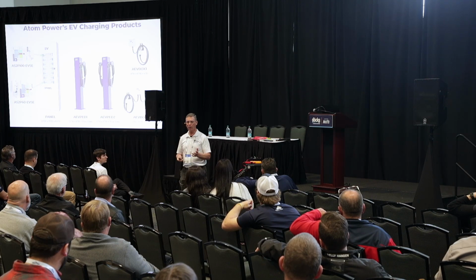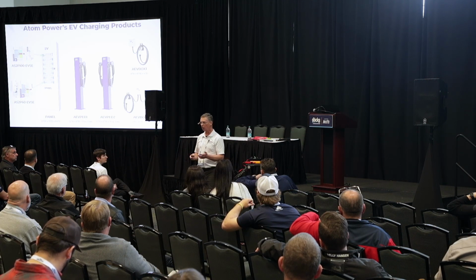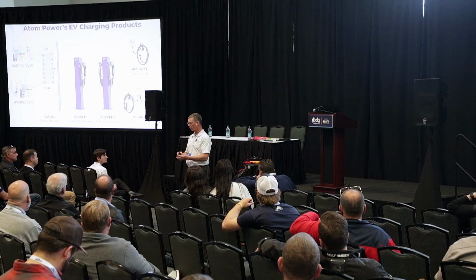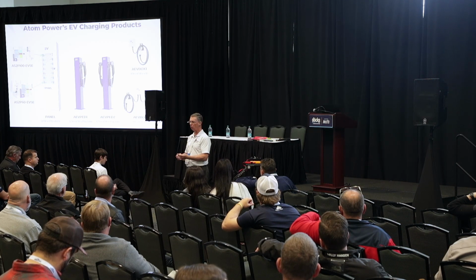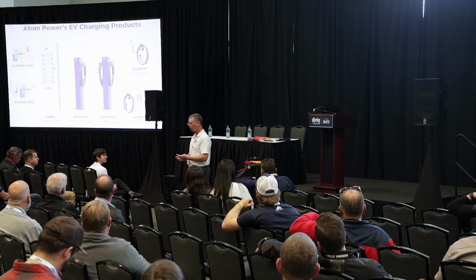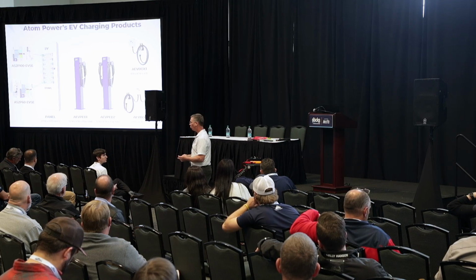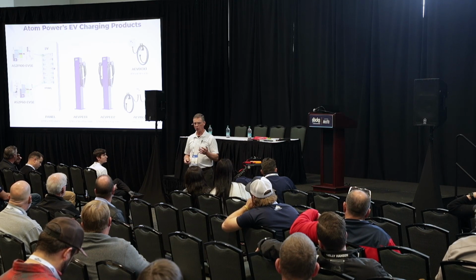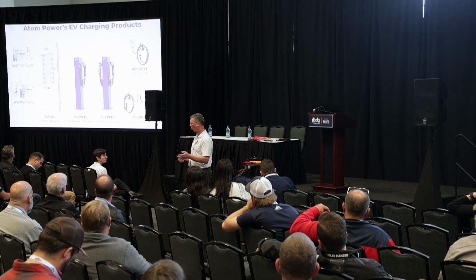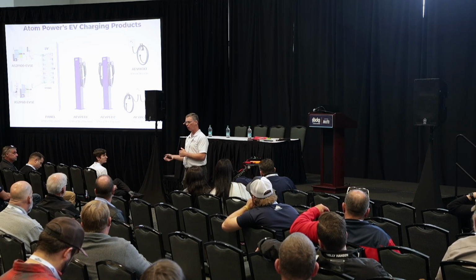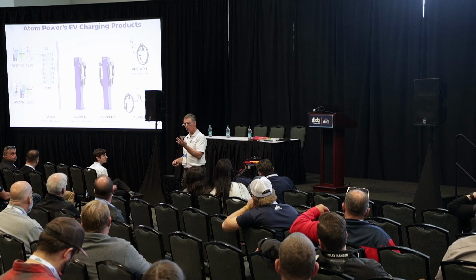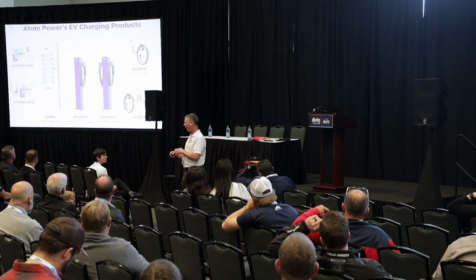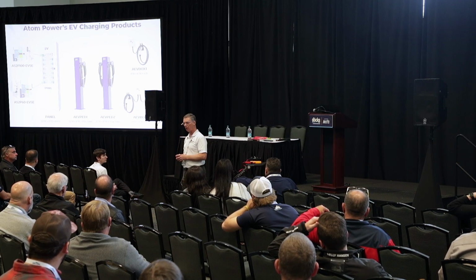It can even be a revenue source, because you could sell priority 1, priority 2, and priority 3 slots to your fleet — unless it's your own fleet, then you can do what you want, but it regulates that power for you. So the benefit as far as cost savings is you don't have to have a 1,200 amp wire or a 1,200 amp service; you only need a 400 amp service to supply 1,200 amps worth of power and distribute it in that fashion.